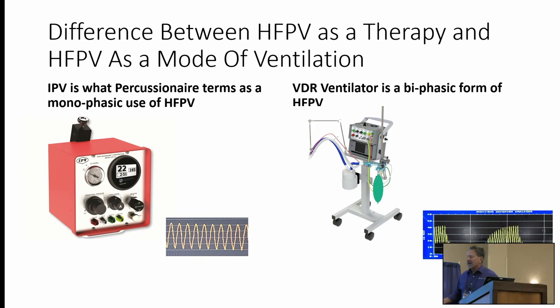So I wanted to put this up to show the difference between high-frequency percussive ventilation as a therapy and as a mode. If we're using it as a therapy, what we call this is a monophasic device, using the same pressure going to the same peak pressure or amplitude. But if you use it in the form of ventilation, we call it biphasic - it has two pressure thresholds. The lower threshold is what you commonly call PEEP, and the upper pressure threshold is the inspiratory phase.